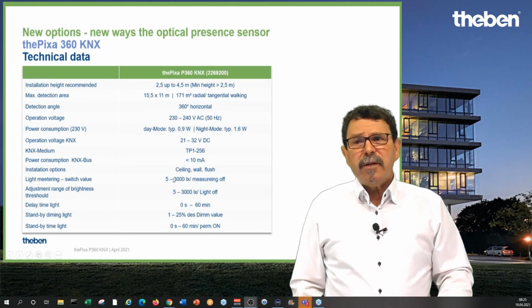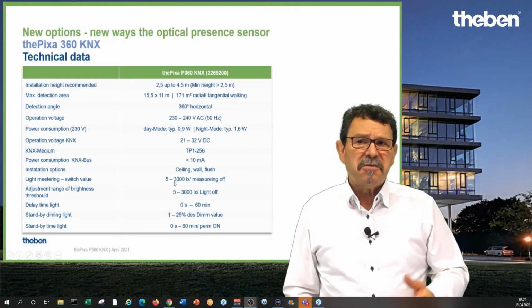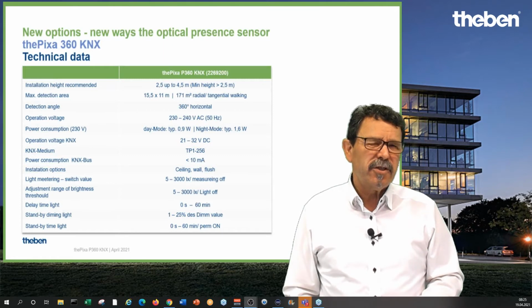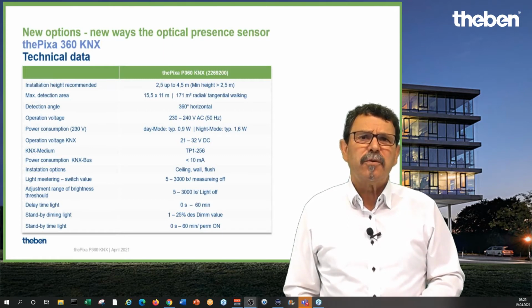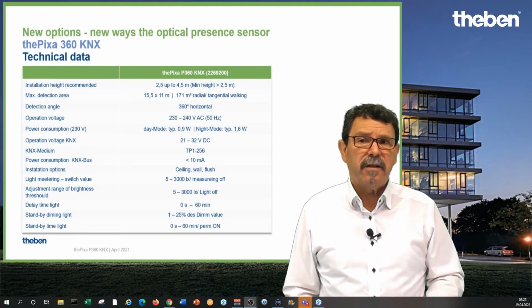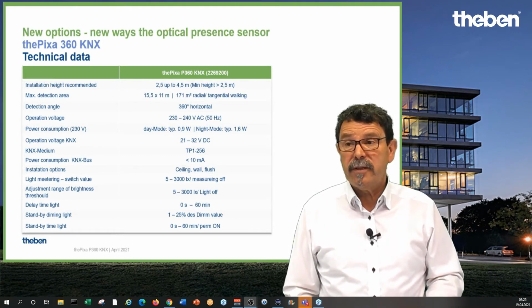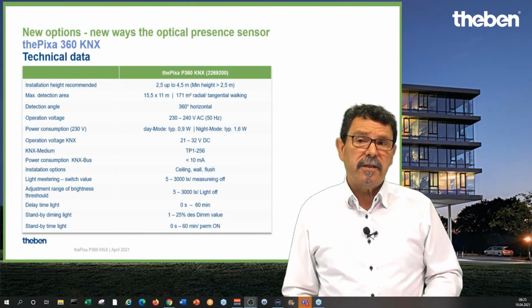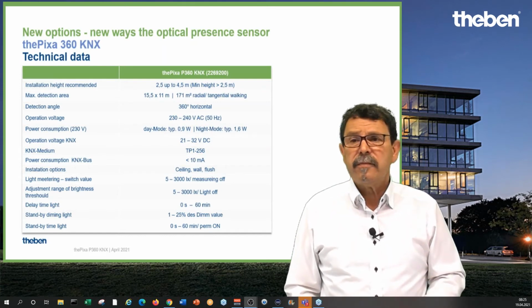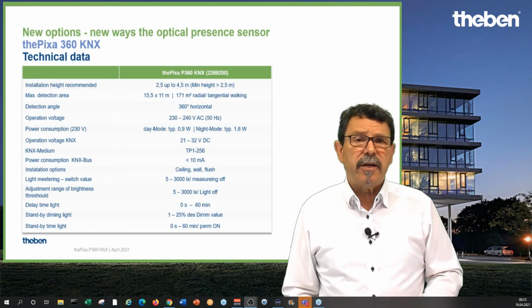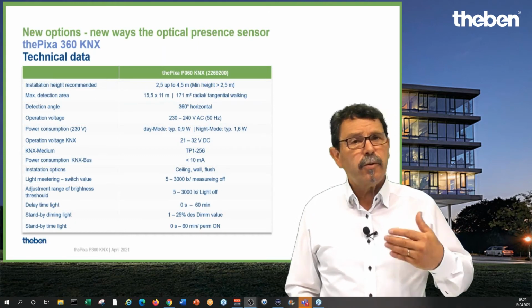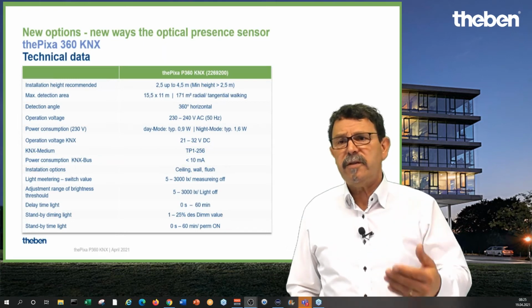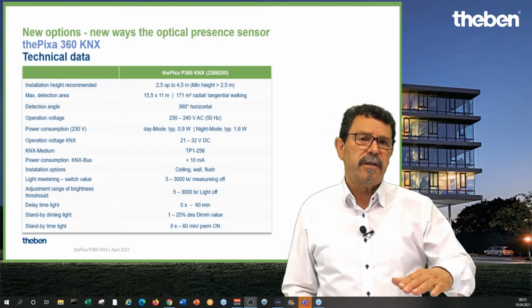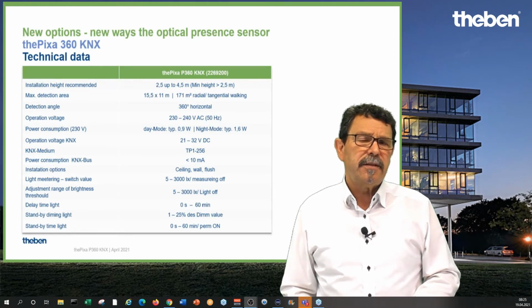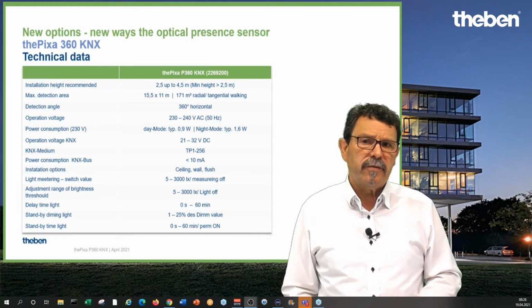Basically the light metering we have here is more than good enough. Starting from 5 lux, which is rather dark, up to 3000 lux, we can set it. We can deactivate the light metering if you like. We can adjust it in terms of delay times, and we can do standby values as well. So when there is no occupancy, no movement, no activity in a corridor for instance, we can send a telegram and go down between 1 and 25%.